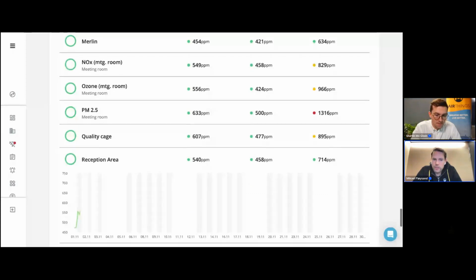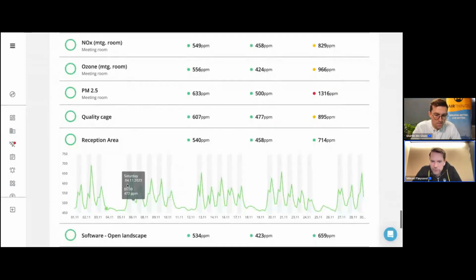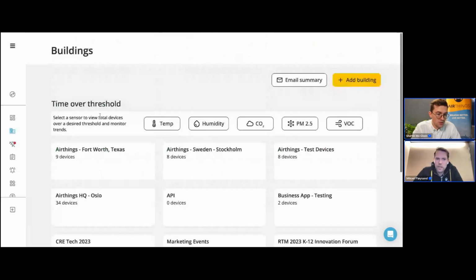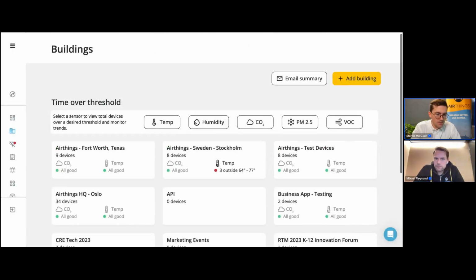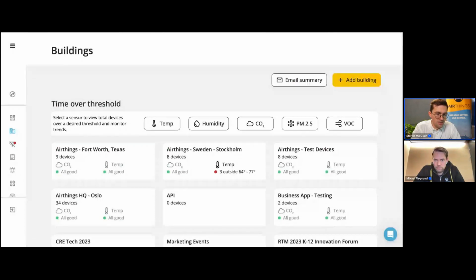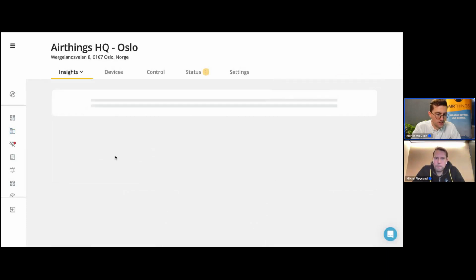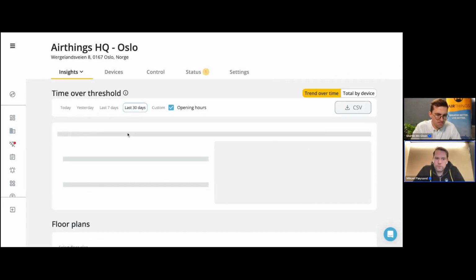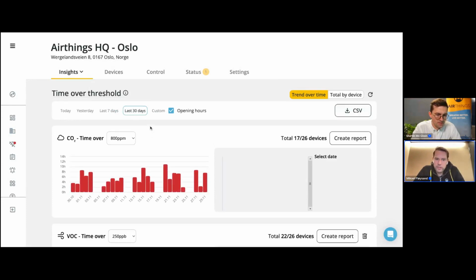Yeah, so if you use the reception area, if every room was like this, never above 650, 700, then I would start considering, okay, maybe we can reduce the volume of air that you ventilate. Or, what we're going to look at next, maybe the schedule in how you ventilate the space is an opportunity. So in the interest of time, Mikael, we've looked at the IAQ report, time over threshold. Just glance over and see how you can select CO2, and then we jump to space utilization. You do the same thing for CO2 here, and you would basically be inverting it.